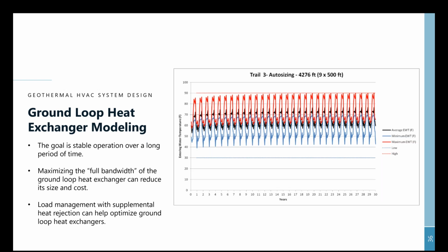So while this represents very stable operation, what it's showing you is that there's a little bit more bandwidth left in this field, and if there are ways that you can do load management to allow the temperature to get a little lower, you'll be utilizing your geothermal resource better. Load management is the idea of the hybrid geothermal system, where typically in cooling dominated climates, where you're doing much more cooling than heating, load management means that you're adding some sort of supplemental heat rejection to help optimize the ground loop heat exchanger.